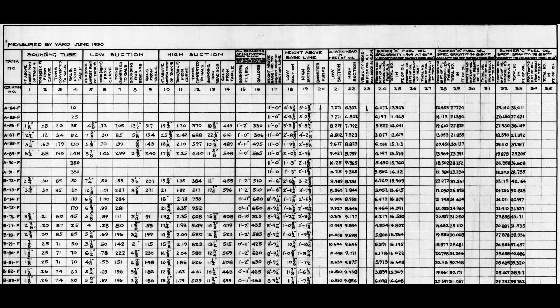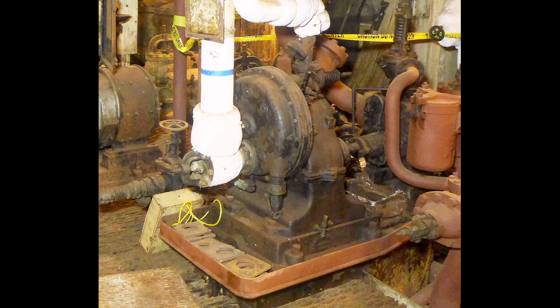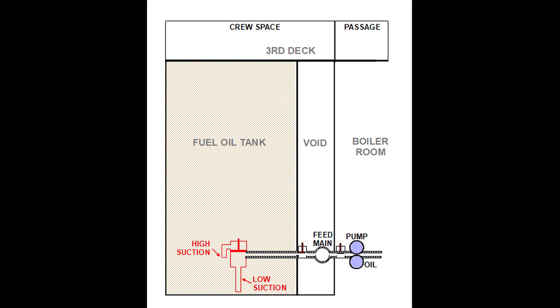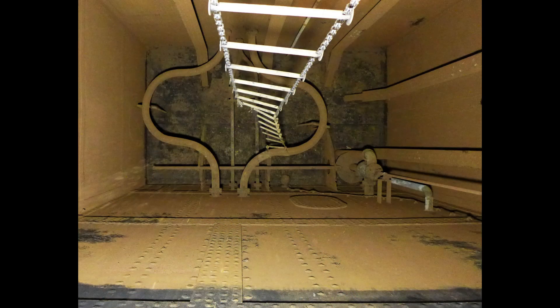In spite of its variability, oil had to be provided to the boiler rooms at a steady rate. Two booster recirculating pumps in each room accomplished this by providing oil at a controllable constant pressure to heaters and then to fuel oil service tanks. If we look inside a tank, we can see a valve located at its bottom. Since we already know there's a stop valve on the feed line outside of the tank, what was this used for? The first clue is given by these discs on the surface of the third deck. A close look at one shows it to be a remote valve operator with engravings that identify it as fuel oil suction and fill, that includes the important letters H and L. These operators switch between either high or low pickups on the valves that draw fuel from the bottom of the tank.